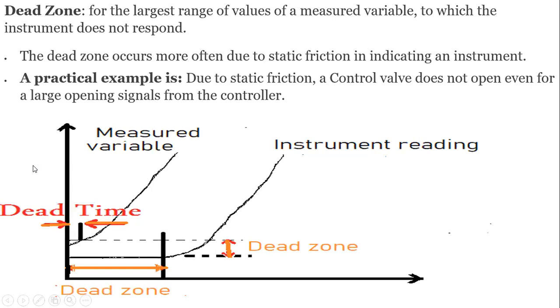Dead zone is the largest range of values of a measured variable to which the instrument does not respond. On a graph of measured variable versus instrument reading, the difference along the x-axis is the dead zone, and the time lag is the dead time. A practical example: due to static friction, a control valve does not open even for a large opening signal from the controller because it has a certain dead zone before it can respond.